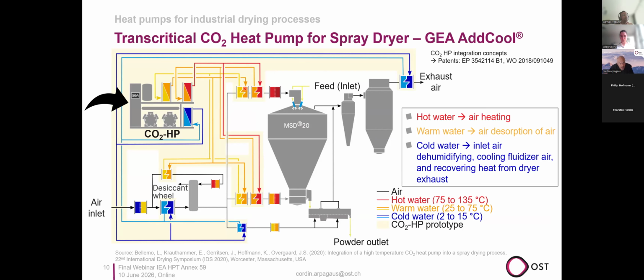And this is a solution from GEA, the so-called AddCool system. So we have here also a CO2 heat pump that has 2 gas coolers. There is an intermediate secondary loop for hot water. This hot water goes into the air stream to heat up the air for the spray dryer, which is shown here. And then the cold side of the CO2 heat pump can be a cooling loop. So both sides of this heat pump are beneficial. So we achieve a high COP, heating and cooling COP.